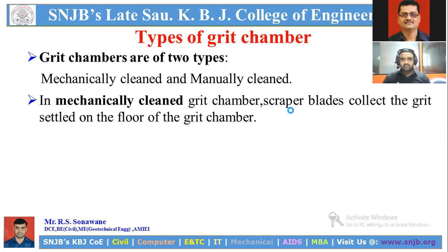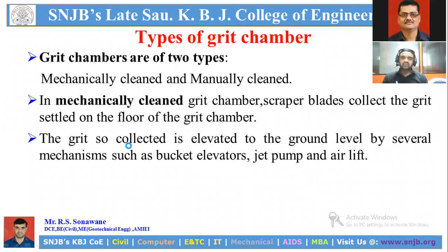So what does the scraper mainly do? It collects the grit, and the grit which has settled down on the floor is collected by the scraper blade. Such a grit chamber is called a mechanically cleaned grit chamber. Now the grit so collected is elevated to the ground level by several mechanisms such as bucket elevator, jet pump, or air lifts.